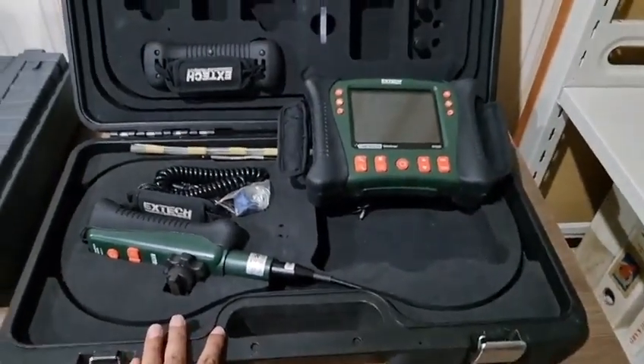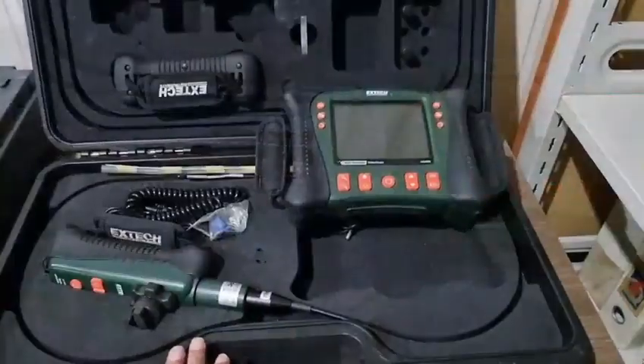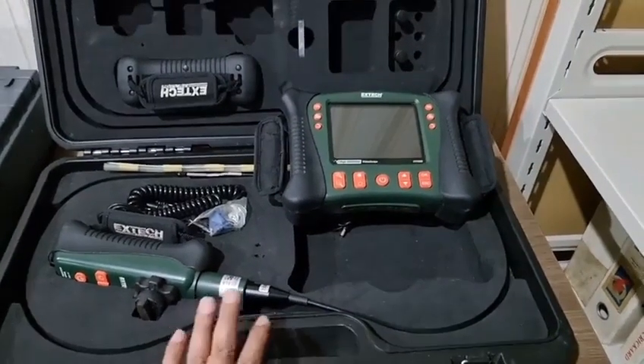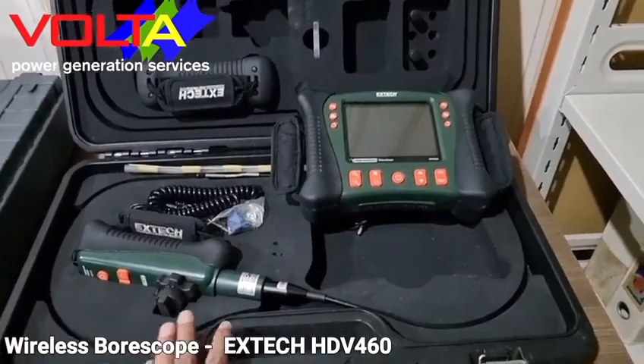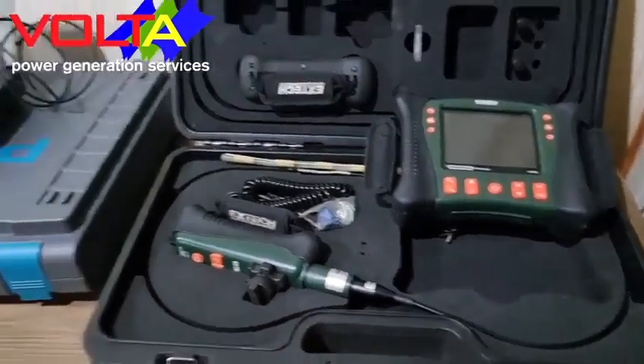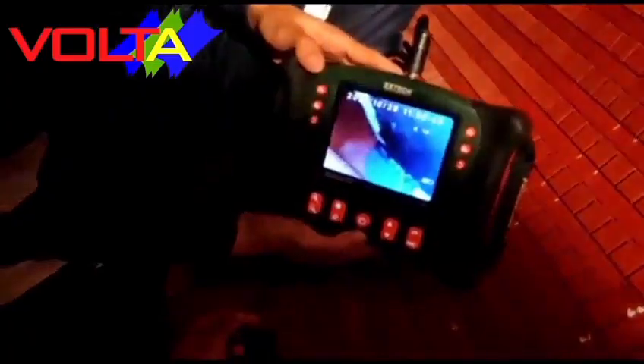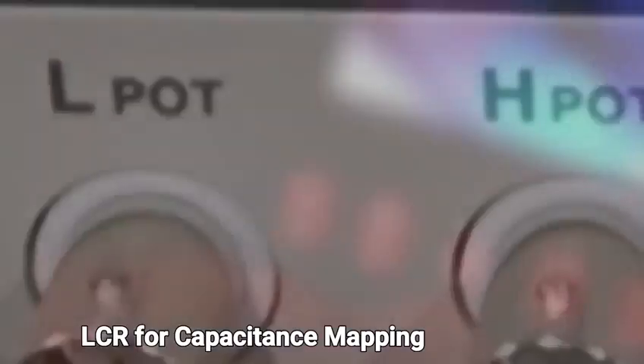For an HDV video scope camera to inspect inaccessible areas, we use the Extech wireless borescope type HDV460. Our instrument is provided with 4 millimeter and 6 millimeter video probes, allowing inspection in very narrow spaces — for example, inspection of PD tracking through the ventilating duct of the stator core.